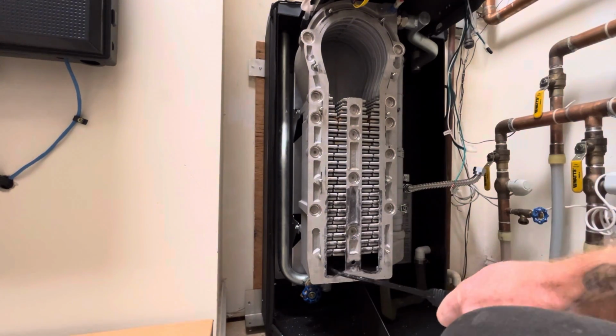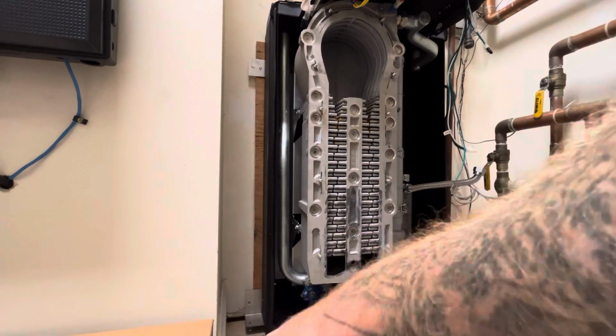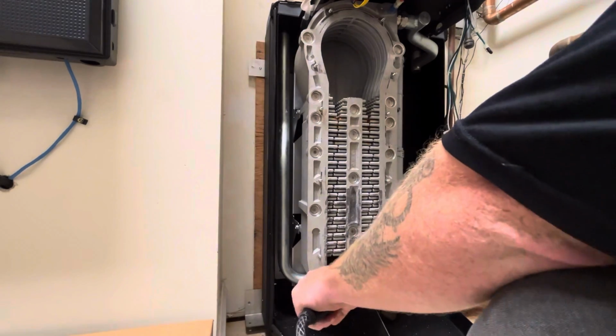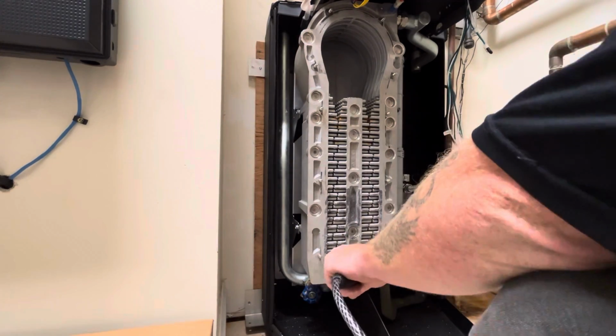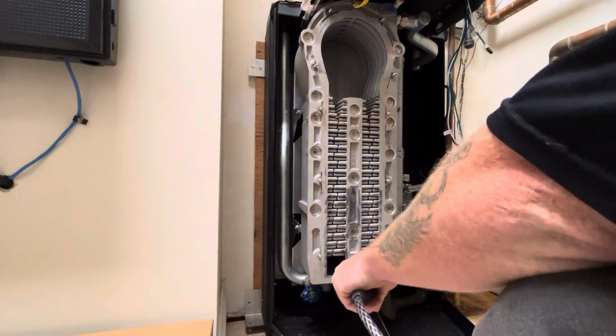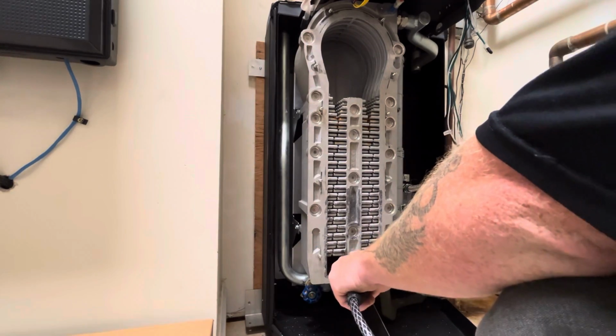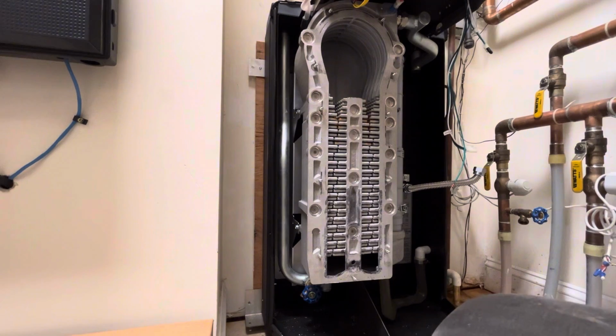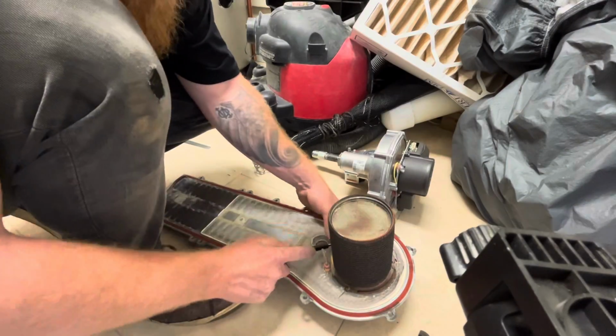You want to make sure that you clean everything out of the bottom of the heat exchanger here, because if you don't, the condensate will sit there and it will rot out through the bottom of the heat exchanger and it will leak. This is actually the second one of these boilers that this guy has, and that's what happened to the first one. So anyway, now we're going to work on the burner assembly.